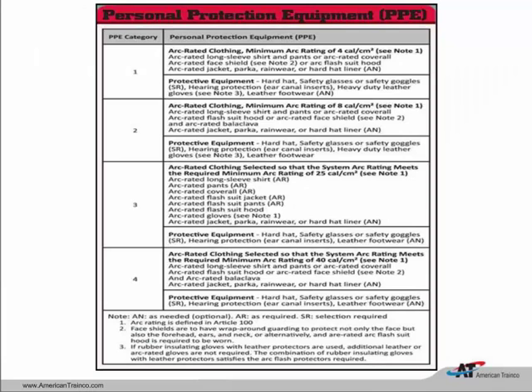So if we come to this slide, we see PPE Category 4. This would be a full-blown flash suit, and we would have to have those arc-rated gloves on in conjunction with that flash suit. So this method, remember, is only going to be used if we did not do the full-blown arc flash risk assessment.